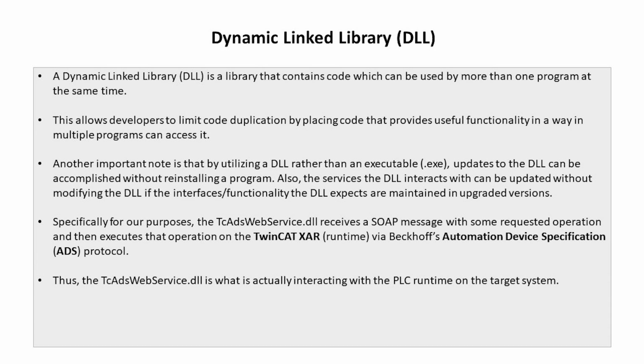So specifically for our purposes, the TcAdsWebService.dll receives a SOAP message with some requested operation and then executes that operation on the TwinCAT XAR. And this is using Beckhoff's Automation Device Specification, the ADS protocol. The TcAdsWebService.dll is what's actually interacting with the PLC runtime on the target system.